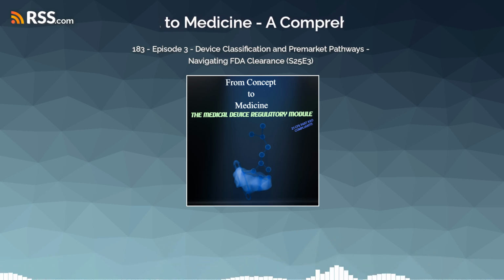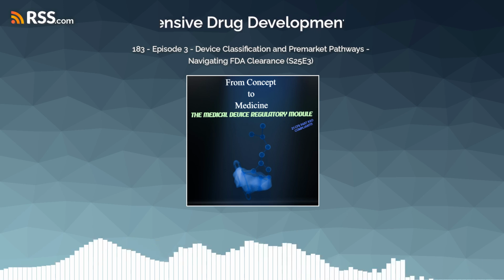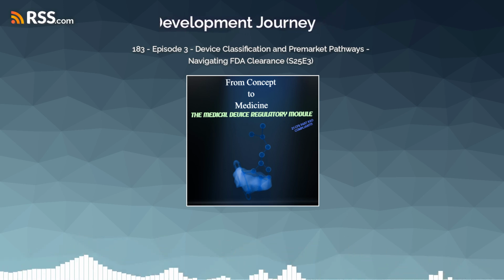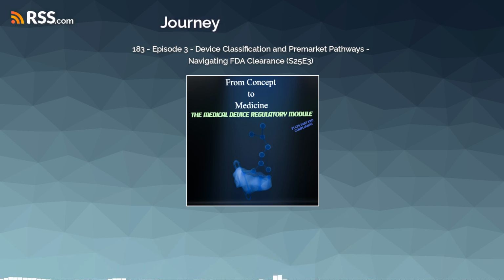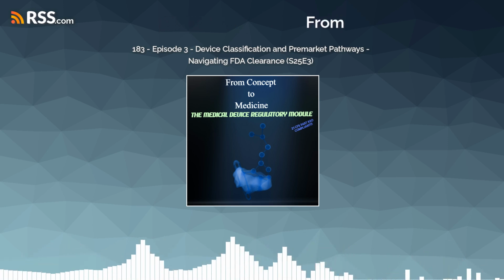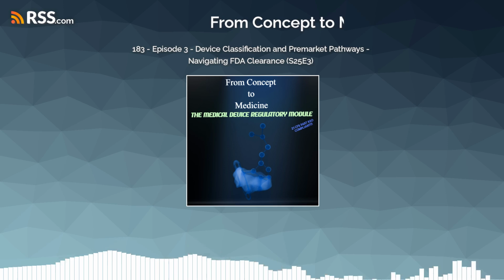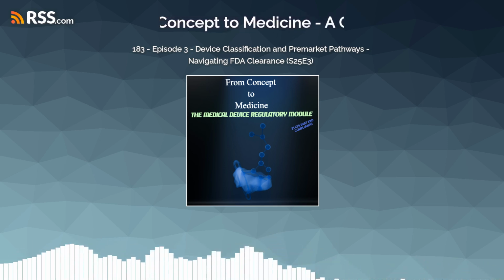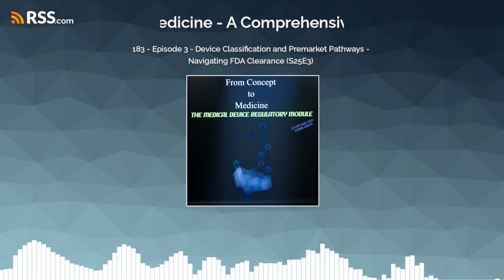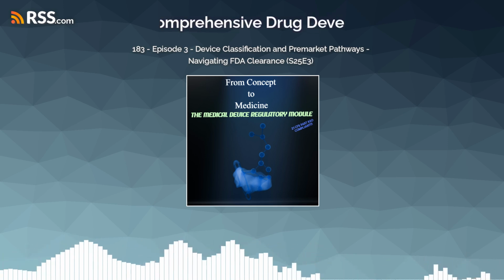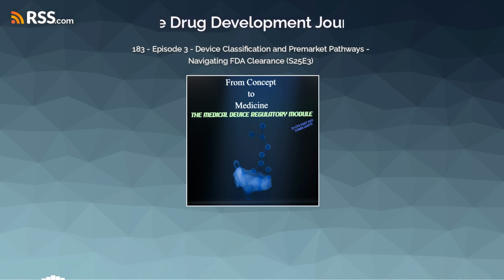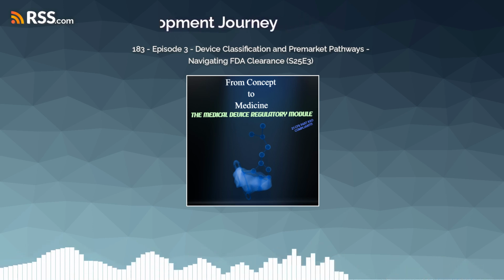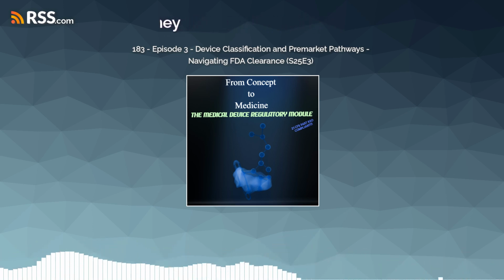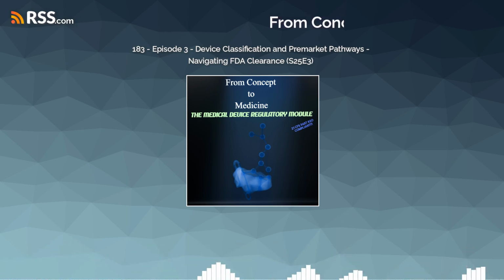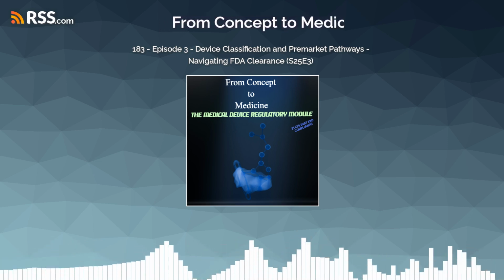Which makes sense. But obviously the stakes go up. What about the next level, class 2? Right. Class 2 devices pose a moderate risk. And because the risk is higher, they need something more than just general controls. They need special controls. Okay, what does that mean in practice? Well, it's not a single thing. Special controls are tailored to the device type. They might include mandatory performance standards, special labeling requirements to ensure safe use, maybe rules about post-market surveillance, tracking how the device performs out in the real world. And they often have to follow specific FDA guidance documents, too. So extra requirements specific to the device layered on top of the basics.